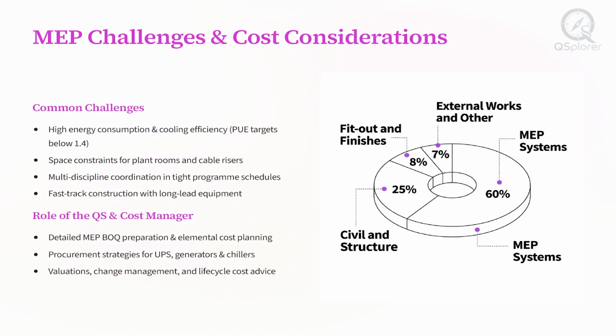Data center projects present several unique challenges for both engineers and commercial teams. One of the biggest challenges is energy efficiency because cooling systems consume a significant amount of electricity. That's why many projects target a low power usage effectiveness, or PUE, typically below 1.4. Space planning is another challenge, as large plant rooms, cable risers, and equipment layouts must all be carefully coordinated. Fast track construction schedules also add complexity because critical equipment such as UPS systems, generators, and chillers often have long manufacturing and delivery times.